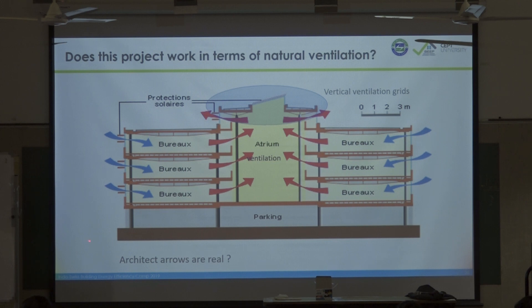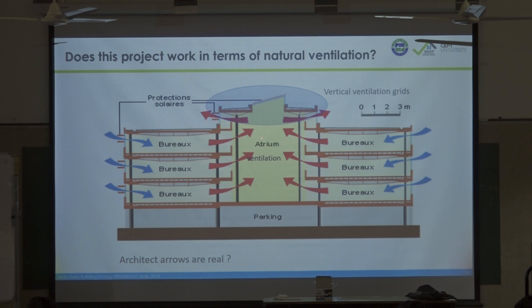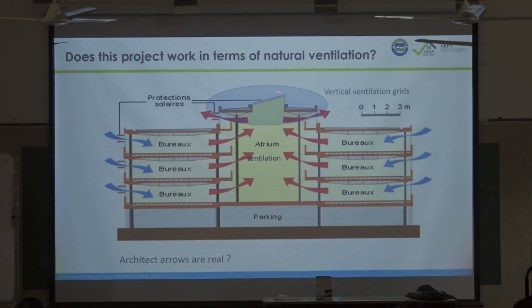Does this project work in terms of natural ventilation? Now that you are junior experts in natural ventilation, what would you change as an architect? The problem here: you cannot generate a low pressure with this configuration because you have lots of friction and cannot accelerate the wind. The suggestion: remove everything, consider the atrium as outdoor, and design a low pressure shaft of at least 2–3 meters there.